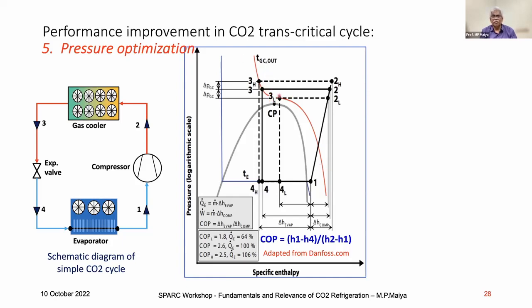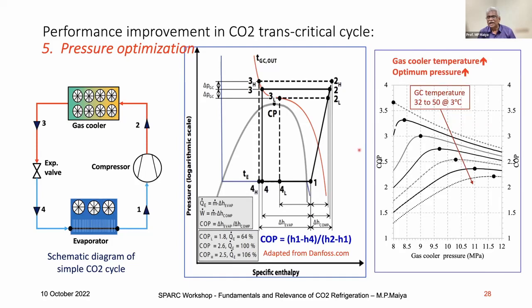You can see from here to here, you can go. Some increase in power is required, but the cooling benefit is large. Then if you further increase the pressure, the same amount of work input is required, increasing, but the benefit is less. So obviously there is an optimum. You can see here that as the ambient temperature, gas cooler temperature, increases, the optimum pressure will increase. This is one way. These are low-lying fruits, and you can use this technique to optimize.